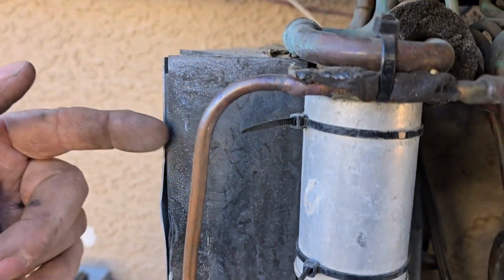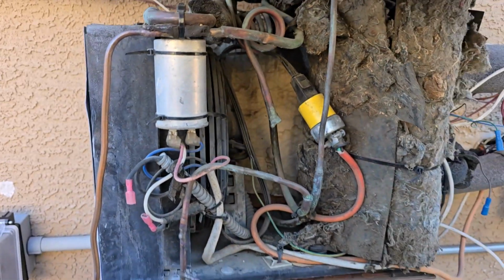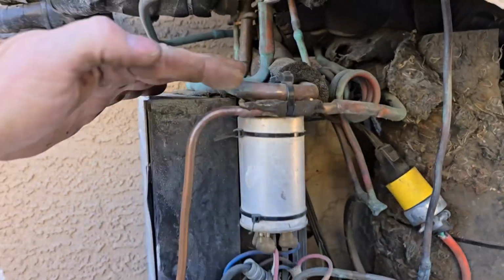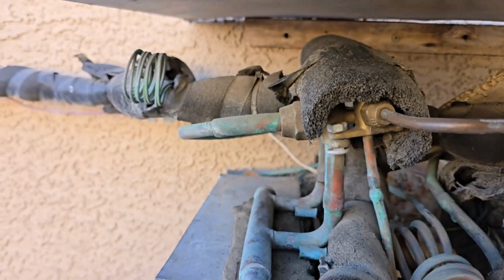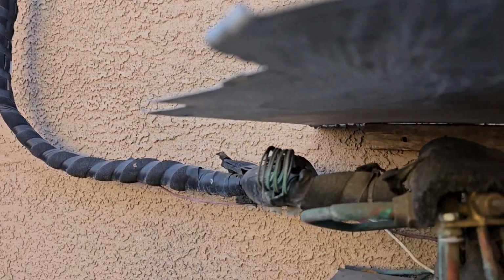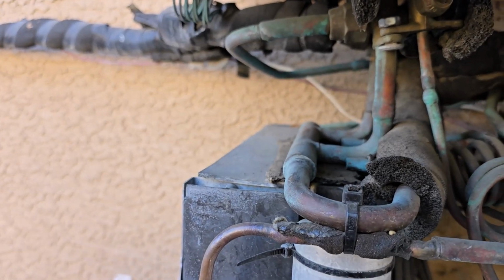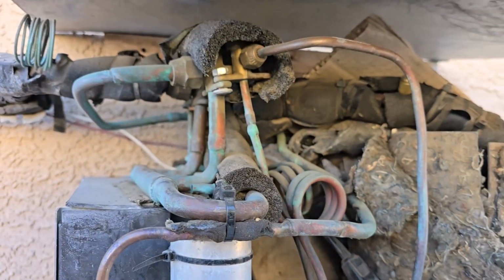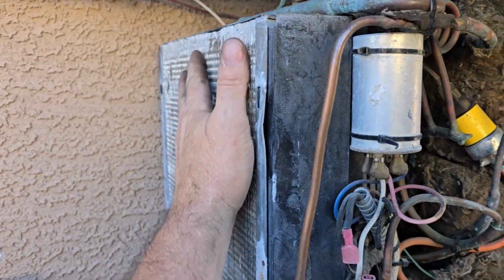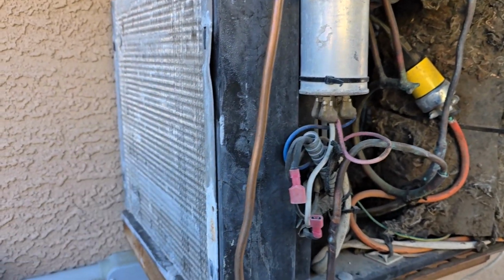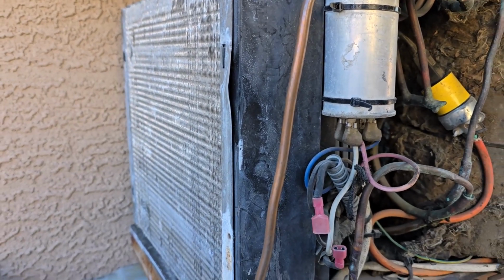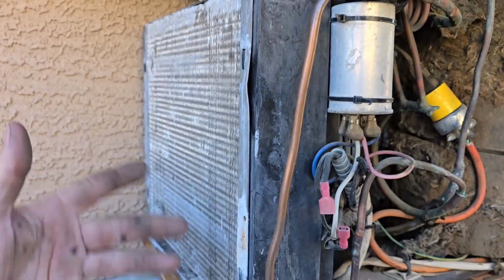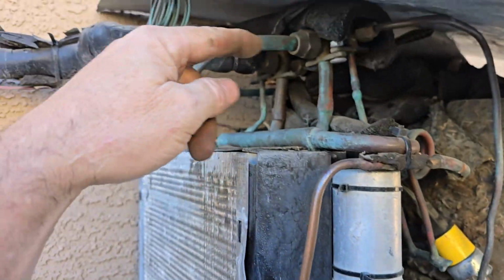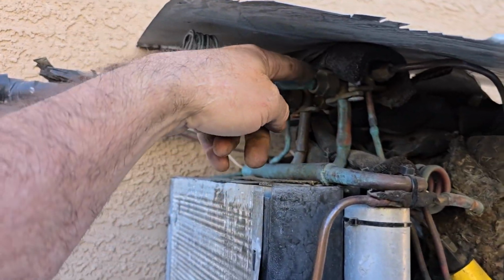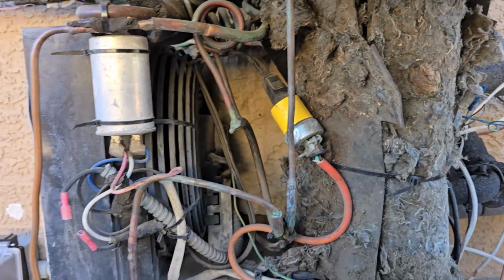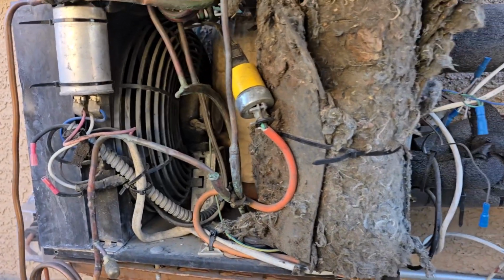And before I had that hooked up, I was using this one. So one of the revisions I did was I put this on here so I could switch this. Like in the summer, I would use that coil in there. And I've kept that through the winter too, just because it doesn't freeze up in that room, and there's way more heat load in there from my inverter and everything that's in there. Where this one would like to frost up, and sometimes it would really freeze up, and I'd have to turn it off for a while. I never did add a defrost to it or anything. But all I have to do to run this coil is plug the fan wire in and pump down that circuit and open up this circuit, and it works. I can use either the outdoor evaporator or the indoor one. So that's just how it works.